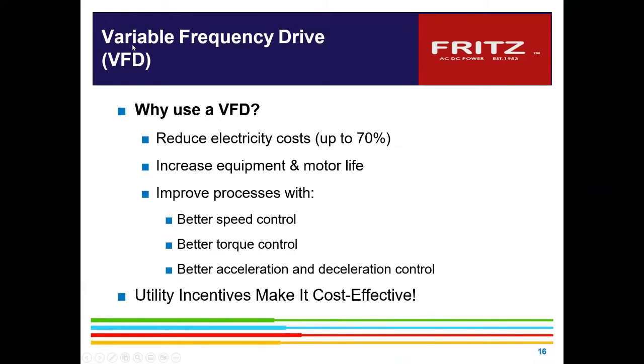So the reason I bring that up is that when you are looking to put in variable frequency drives, they do have advantages. They will reduce the electric cost if it's on a variable frequency pump. It can be cut back to 70% because you get the cube law factor in the pump load. But it's also important to measure your process, of how much water, how much flow you're actually truly needing.